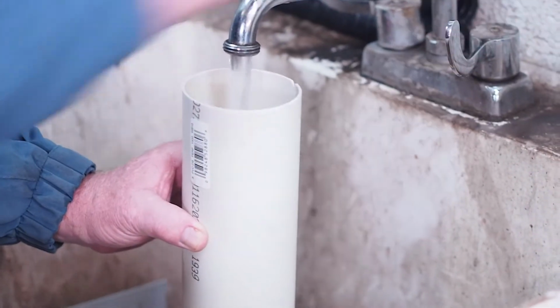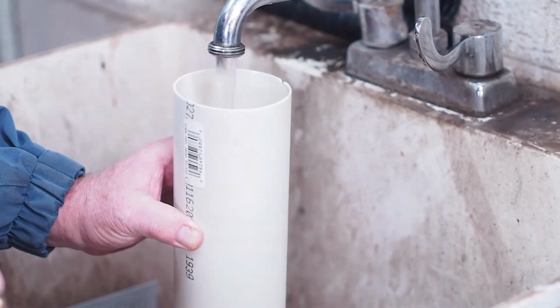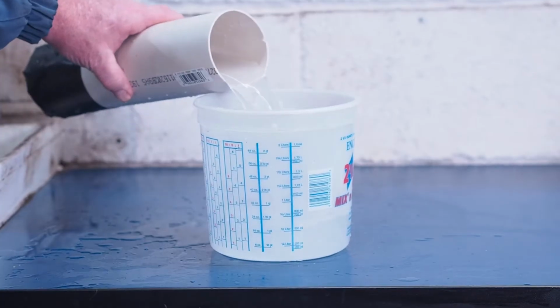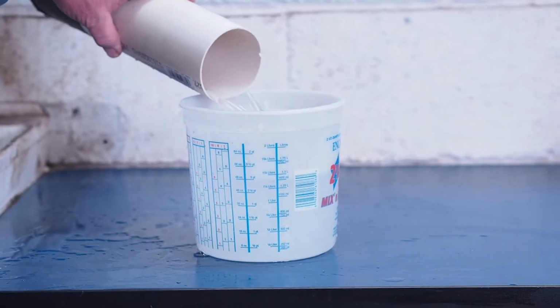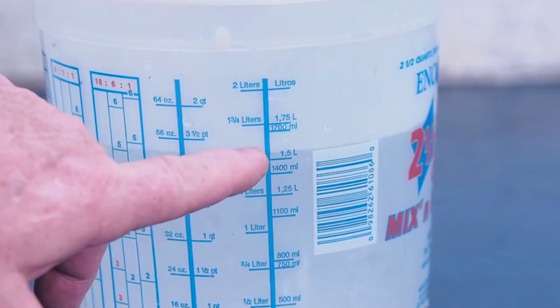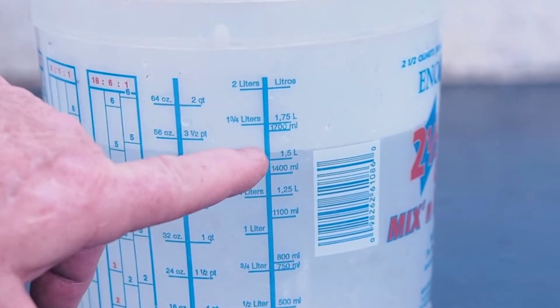3-inch rigid PVC drainage conduit, also with an opening of 7.06 square inches, has a flow rate of about 44 gallons per minute. It follows a smooth downward slope to the sump basin and drains completely. The holding capacity of a 1-foot section of 3-inch PVC drainage conduit is 1 1/2 liters.